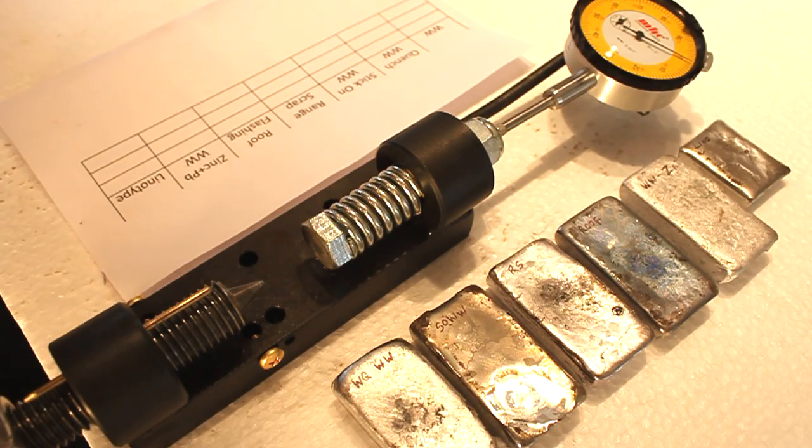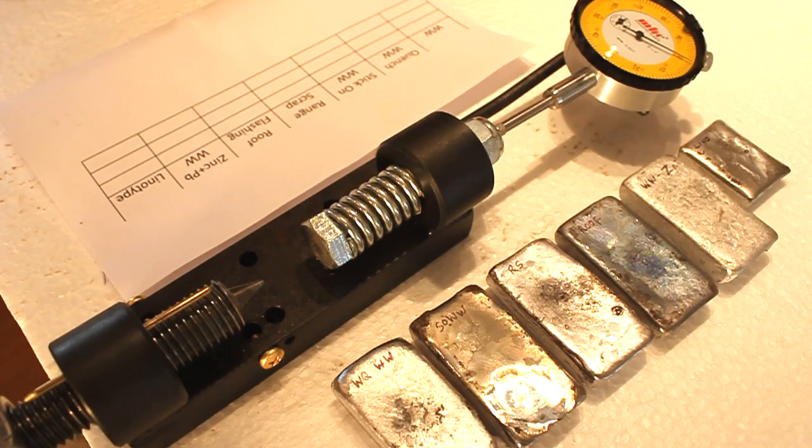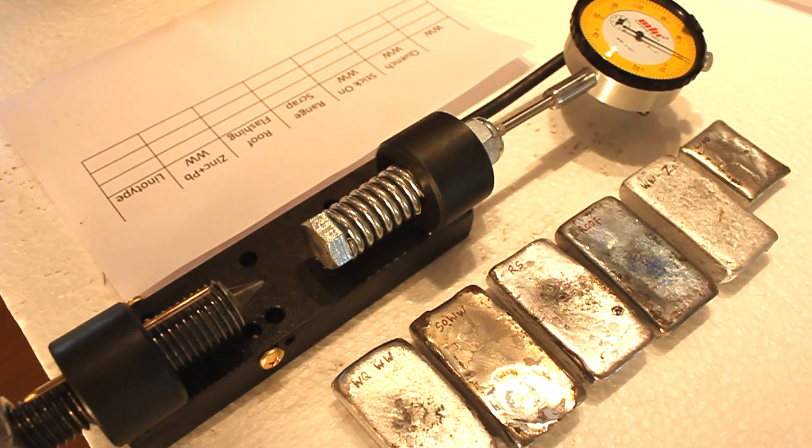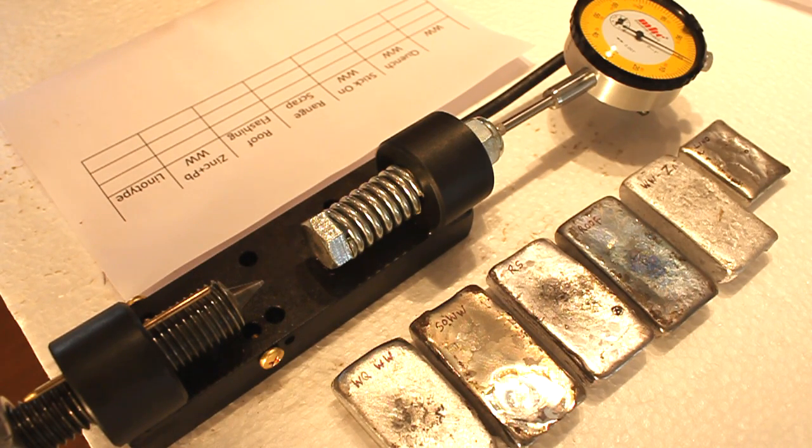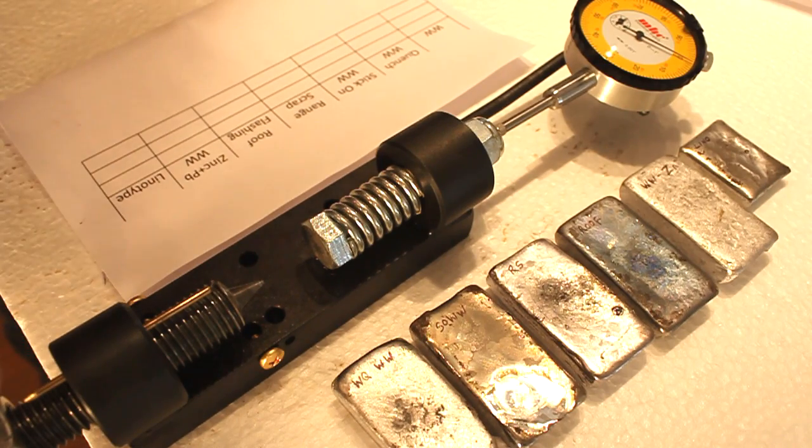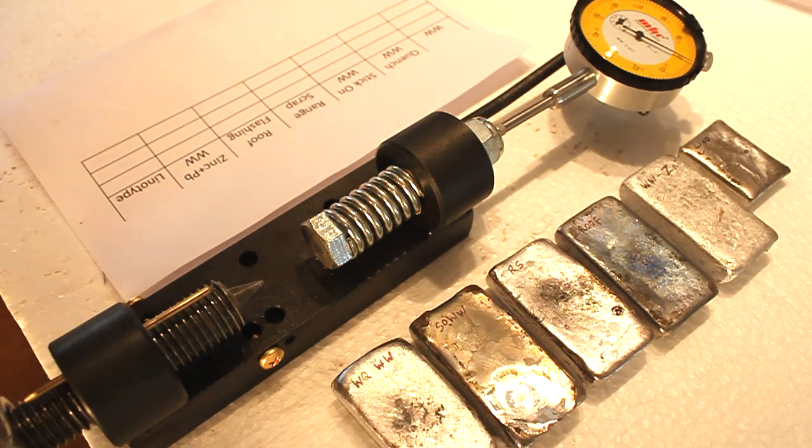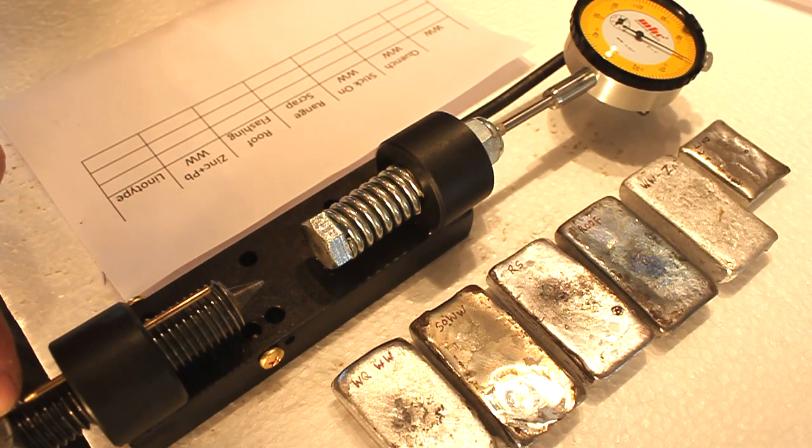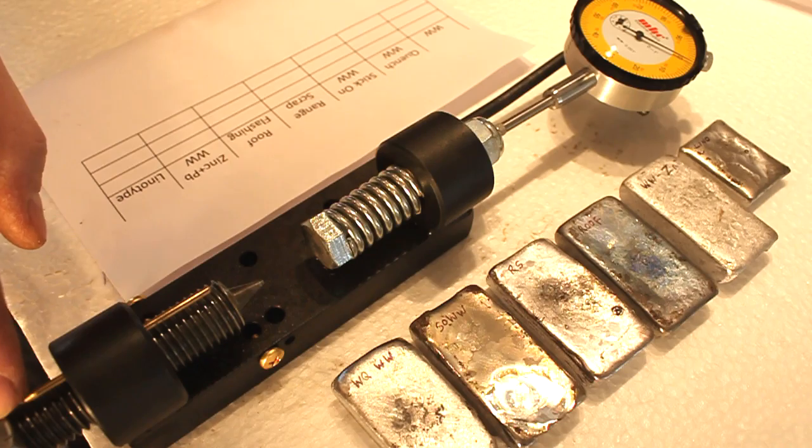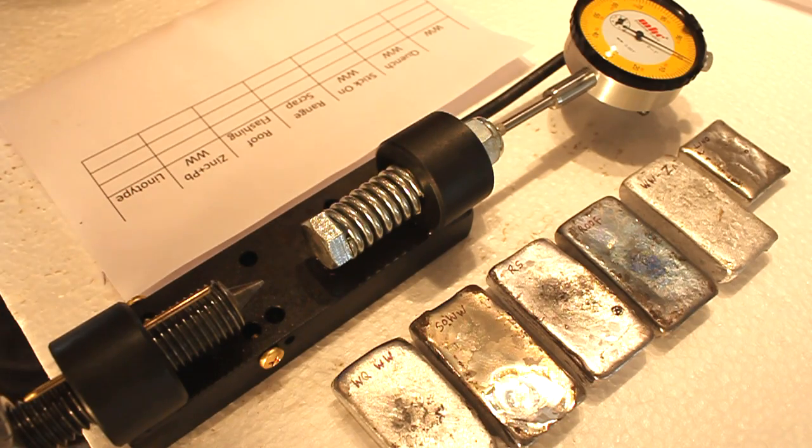The way this unit is supposed to work according to the instructions, it says run the screw point until it just touches the sample, and it should preferably be on a flat spot. After the point just touches the sample, note the exact point marker which would be here on the bolt head. It's got marks on it. It says rotate it exactly one turn and then read the indicator.